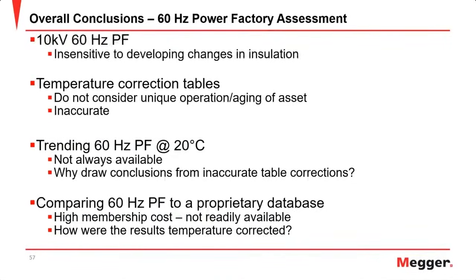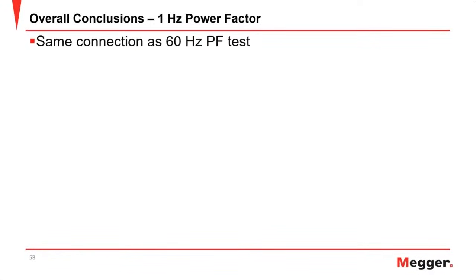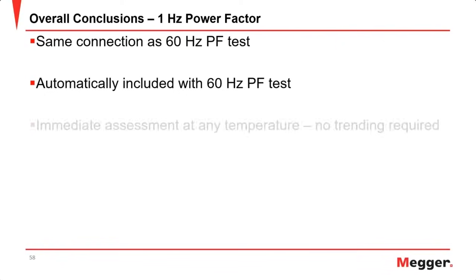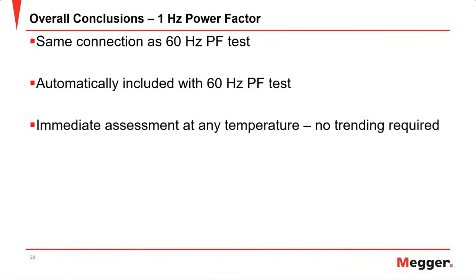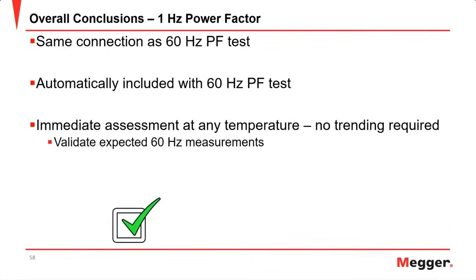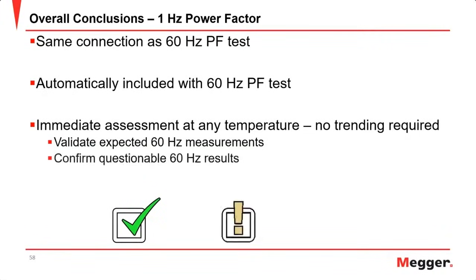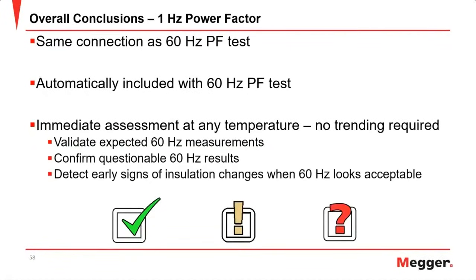So what we do recommend is to perform that 1 hertz power factor test, again, using the same connection as your 60 hertz power factor test, with software that's already pre-configured to do that, and it will give you immediate confirmation of your 60 hertz measurement without any trending required. Of course, you can still do the trending, but this method will get you the best immediate insulation condition assessment for your bushings. To validate when 60 hertz measurements look good, confirm when 60 hertz measurements are questionable, and also to detect early signs of insulation changing.